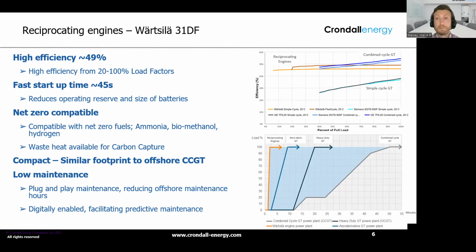Above that, we also have high efficiency across a wide load factor, which is really important for intermittent wind energy, where we're getting lots of wind or low wind, and having to change the loading on those generators. We can achieve that 49% efficiency from 20% load factor up to 100%. If you look at the graph on the top right, below 40% load, combined cycle and simple cycle gas turbines fall off a cliff and their efficiency drops right down, so you're emitting more during those scenarios, which is very detrimental when you've got intermittent renewable energy.